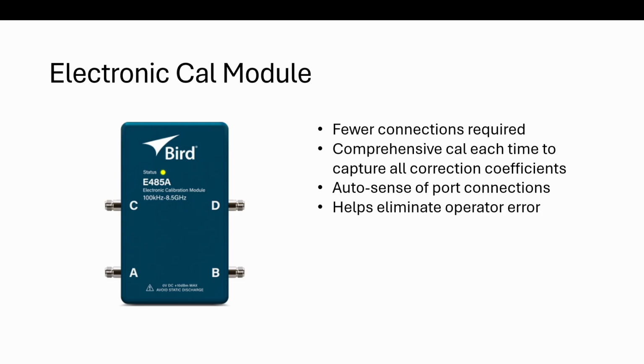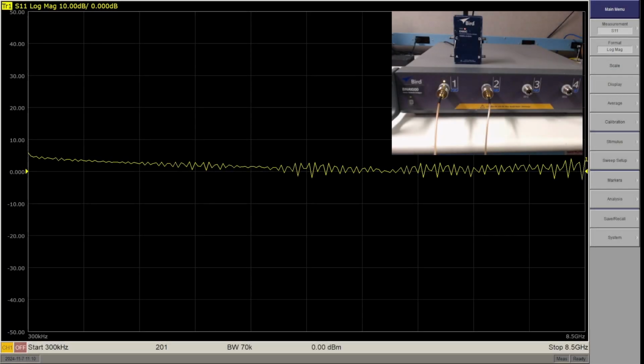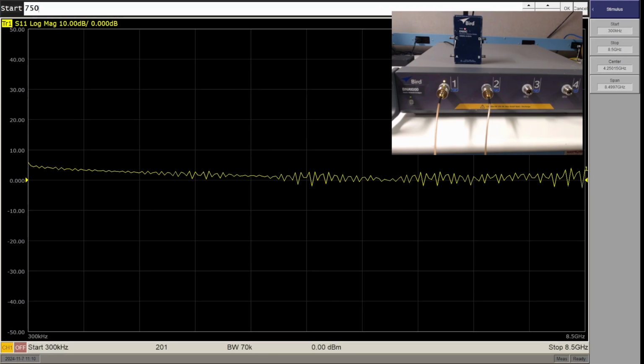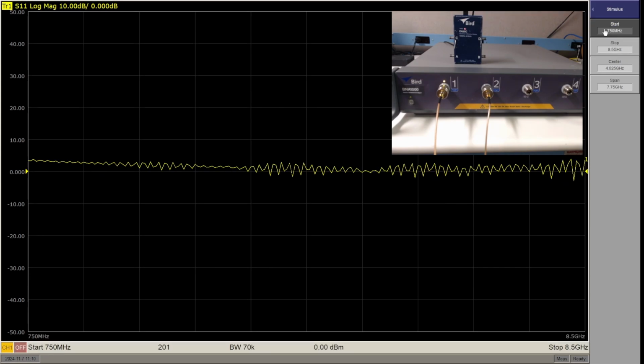Let's see the calibration procedure in action when the electronic calibration, or ECal, module is used. Within the VNA software interface, set the sweep stimulus options to ensure they align with your device test expectations. In this case, we will set a start frequency of 750 MHz and a stop frequency of 950 MHz.